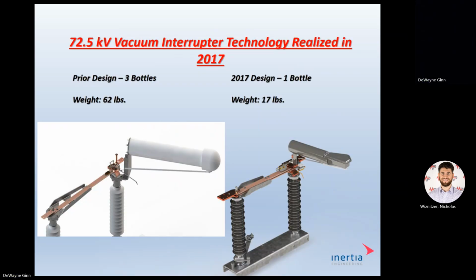This is very unique. We worked with Eaton, who we get our vacuum bottles from, for 5 years to try to develop a single 2000 amp bottle. In the past, we used to use the one on the left with a white case on it. It's called a 3-bottle setup. There are 3 individual bottles in there. The downside of it, you had to time them all together when you opened up or made a load break so that they all opened up at the same time. Or if one opened up late, you could have an event. An event would mean that you could have an explosion of this thing.